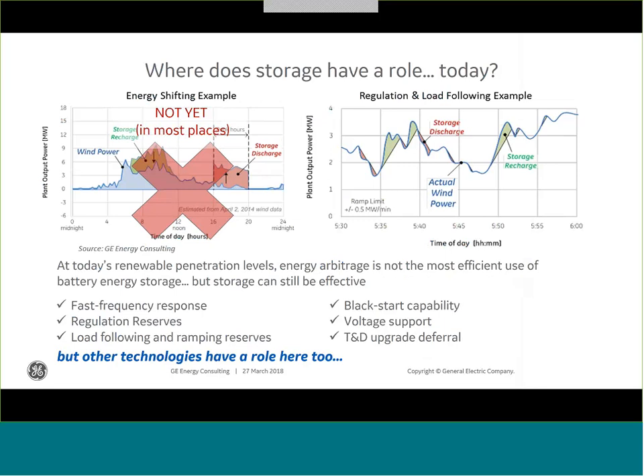So, storage use cases include fast frequency response, regulation reserves, load following and ramping capability, black start, voltage support, and potentially some T&D upgrade deferral. So, rather than upgrade a transmission substation or add a new transmission line or distribution feeder, can we augment what's already there with a little bit of energy storage and defer an upgrade? There's a lot of talk in the industry about using storage for that.